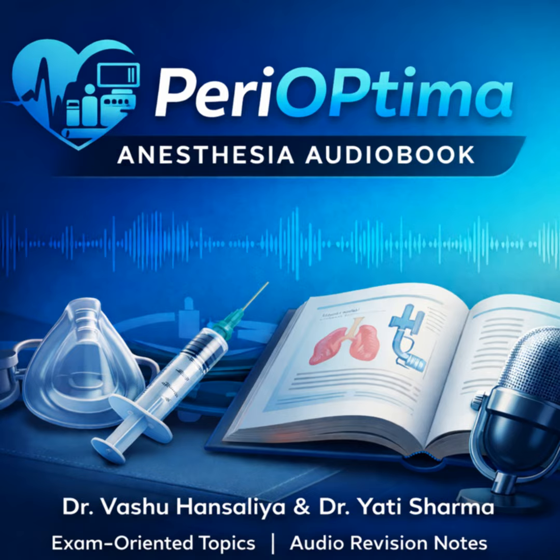What about where simplicity and speed dictate the choice, like in short procedures? For very brief, simple procedures, especially those involving an inhalation induction, the Mapleson D or Bain is often chosen. They have a shorter time constant than the Circle system, which allows for rapid wash-in and wash-out of the volatile agent. It just speeds up the transition to and from anesthesia.